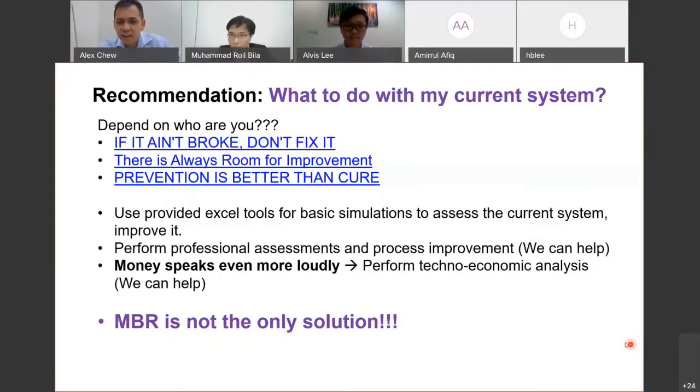Yes, I agree. Maybe I can just add something on this one. Normally, the TOC depends on what type of raw waste it is. For oil and grease, I think everybody knows that above 10 ppm, oil and grease will affect the MBR. So pre-treatment before the MBR is very important, such as a chemical-physical process and aeration.